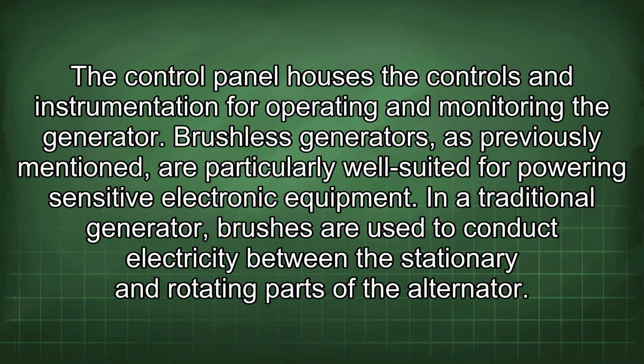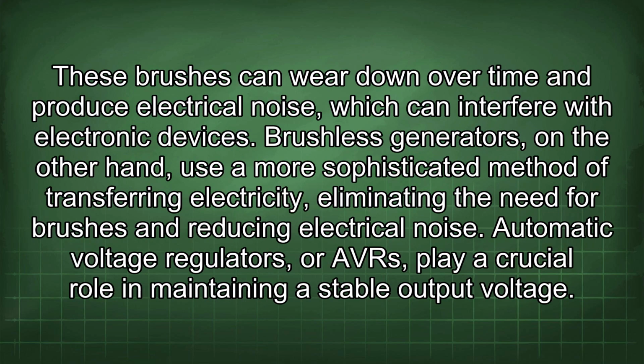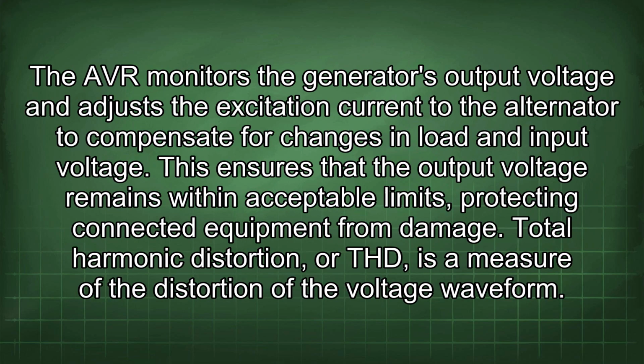Brushless generators, as previously mentioned, are particularly well suited for powering sensitive electronic equipment. In a traditional generator, brushes are used to conduct electricity between the stationary and rotating parts of the alternator. These brushes can wear down over time and produce electrical noise, which can interfere with electronic devices. Brushless generators, on the other hand, use a more sophisticated method of transferring electricity, eliminating the need for brushes and reducing electrical noise. Automatic voltage regulators, or AVRs, play a crucial role in maintaining a stable output voltage. The AVR monitors the generator's output voltage and adjusts the excitation current to the alternator to compensate for changes in load and input voltage.